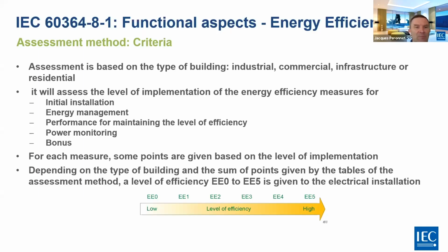So this is what we have in part 6, but we have also part 8-1, which is dealing with energy efficiency. Another type of verification, which is based on an assessment method with some criteria. So this assessment method is based on the type of the building, either industrial, commercial, infrastructure, or residential, and it will assess the level of implementation of the energy efficiency measures for, once again, initial installation, energy management, the performance for maintaining the level of efficiency, the power monitoring, and it also gives some bonus if you have something which doesn't provide benefits to the installation, but gives benefits to the whole network and therefore contributes to use efficiently the electrical energy.